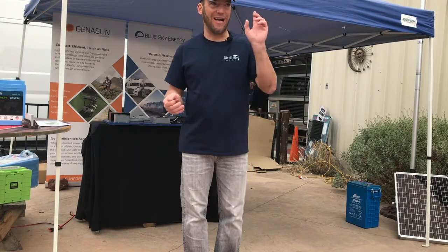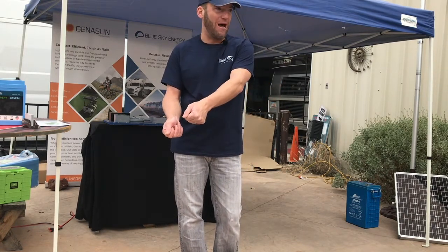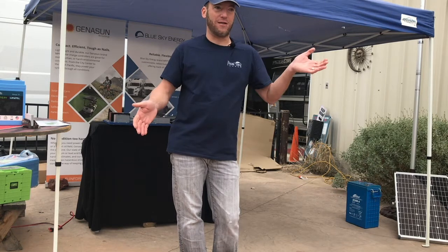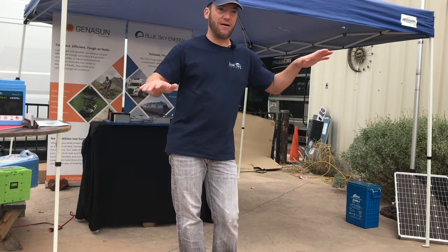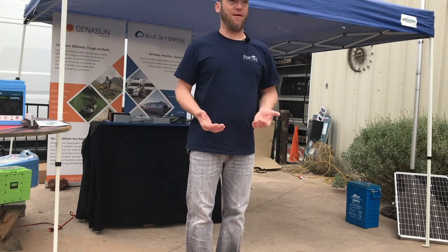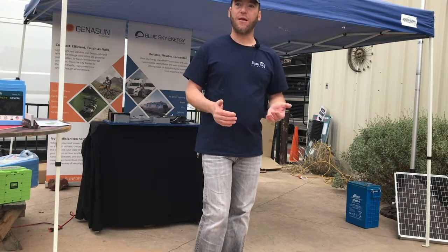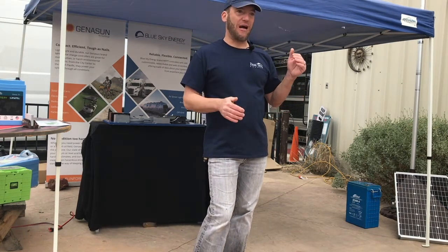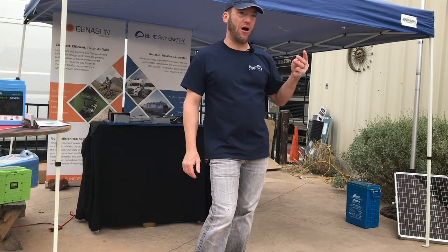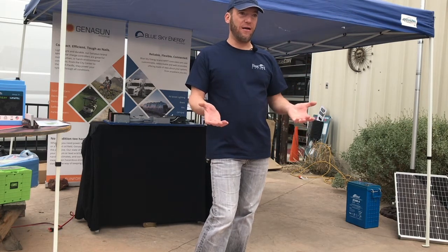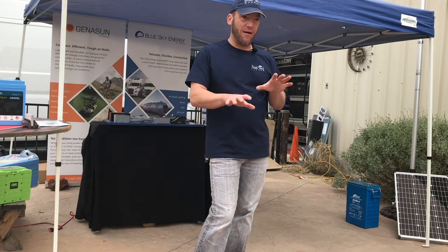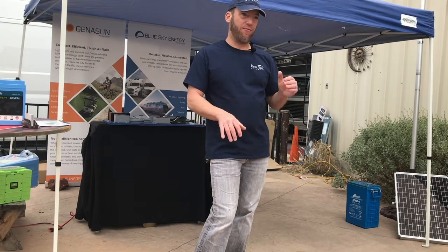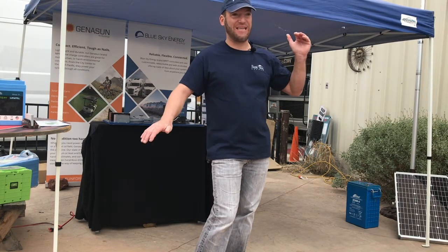As soon as you get to absorption phase, you can check the voltage on your battery. If it's 14.4, 14.4, maybe knock it down a little bit, because you really want to increase the lifespan of your lithium batteries. I'd rather sacrifice a few percent state of charge and increase longevity than stress out the cells, and that's where you get into the fine line, like 14.2 at the battery versus 14.6 at the battery.